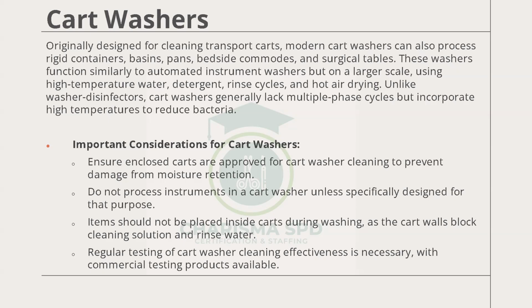And the same thing applies to the cart washers. Originally designed for clean transport carts, modern cart washers can also process rigid containers like the bins and the canisters. We call them canisters at our end. Most of them are metal, actually, hard. Besides the surgical tables and other items the cart washers handle, these washers function similarly to automated instrument washers, but on a larger scale, using high temperature water, detergent, rinse cycles, and hot air drying. Unlike washer disinfectors, cart washers generally lack multiple phase cycles, but incorporate high temperatures to reduce bacteria.